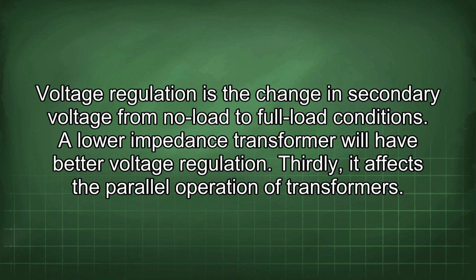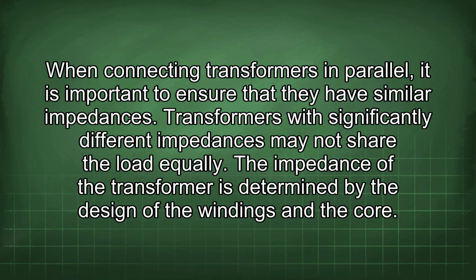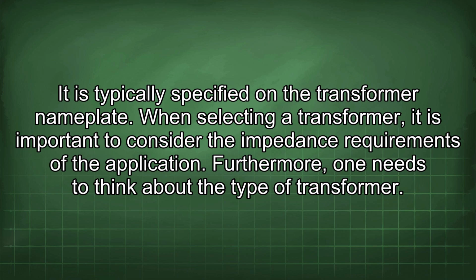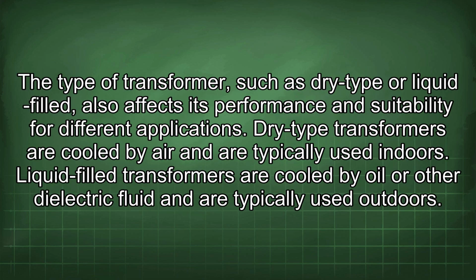parallel operation of transformers. When connecting transformers in parallel, it is important to ensure that they have similar impedances. Transformers with significantly different impedances may not share the load equally. The impedance of the transformer is determined by the design of the windings and the core. It is typically specified on the transformer nameplate. When selecting a transformer, it is important to consider the impedance requirements of the application. Furthermore, one needs to think about the type of transformer. The type of transformer, such as dry type or liquid filled, also affects its performance and suitability for different applications.